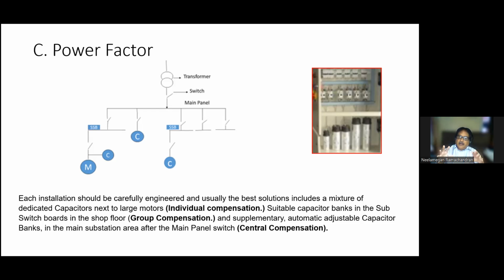Usually we find the power factor compensation is done in the main panel, that is, central compensation. Usually a chunk of capacitors is connected in the power station itself, and there are so many problems. Manually, they have to switch on and switch off depending on the load, during a holiday and so on. Now the APFC panel has come. In my experience, the best is 60%, that is up to 0.89, in the central compensation.